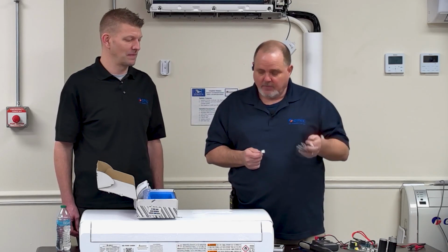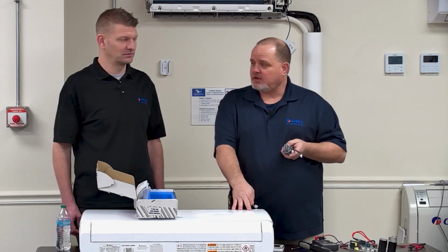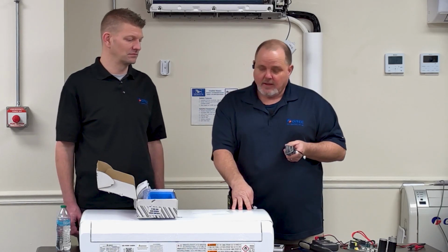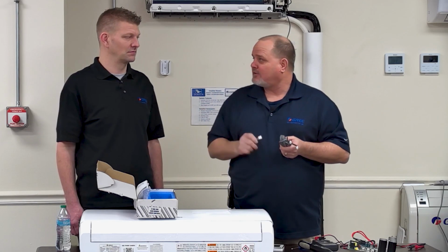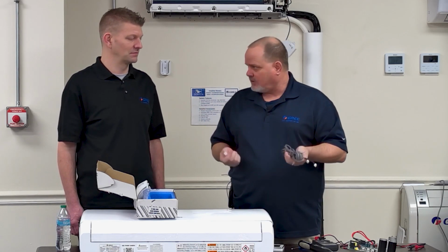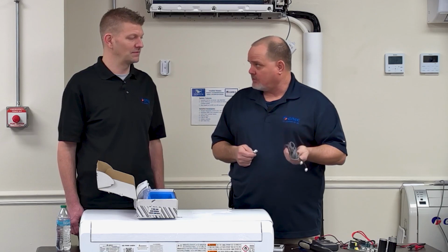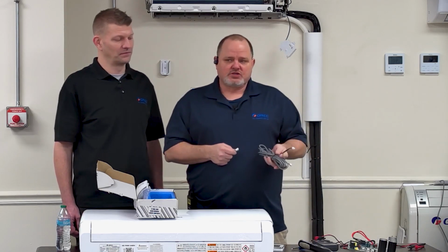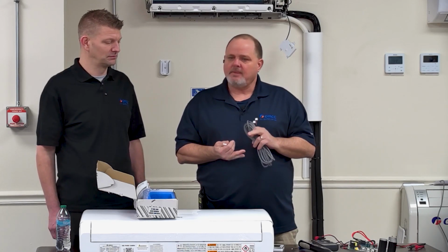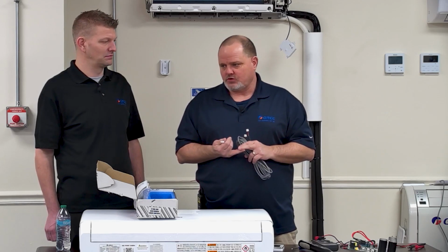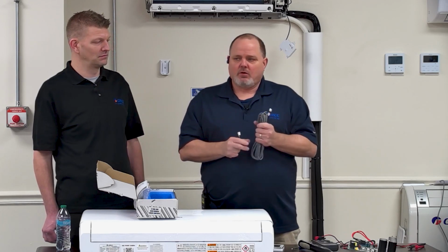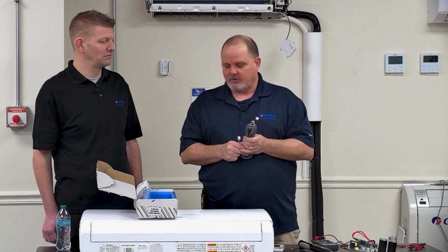But some of the machines, like the wall mounts especially, that plug-in is all the way in the back of that circuit board. So getting to it is not the most friendly way to be able to hook up your service tool. Right. The outdoor machines, the standard MultiPRO and the new Ultra do have the 4-pin Molex plug on the board for you to be able to plug up the service tool. The MultiPRO Ultra B revision did not. On the outdoor unit, there is no port on that board for you to hook the tool up to.